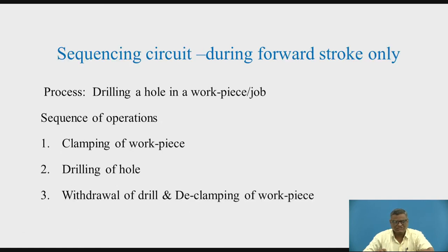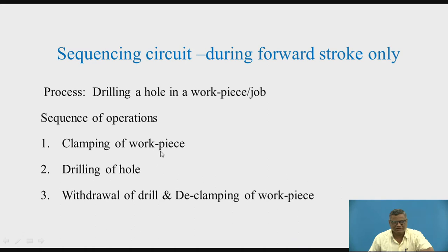We will firstly deal with the sequencing circuit during forward stroke only. Here we make use of linear actuators — cylinders and pistons — with forward stroke and backward stroke. During forward stroke only, we have the sequencing. You can observe that the third operation has been combined with the fourth: withdrawal of the drill and declamping of the workpiece. These are combined, so the forward strokes are completed one after another, and then the backward stroke takes place for both actuators at the same time.